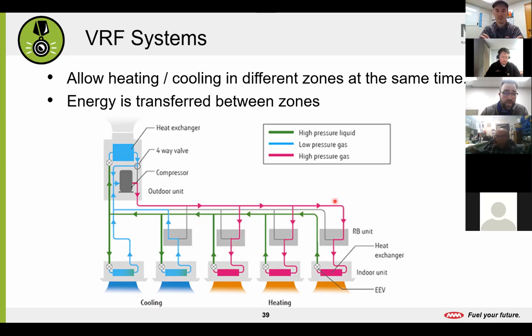Here we have hot gas coming in to our zone calling for heat, and it sends that gas through this rectangle right here. This is our coil. This is where our heat exchange happens. So our blower motor is going to push air across that hot coil. It's going to collect that heat, and it's going to push that into the space. What comes out of these systems is going to be a medium temperature liquid. Now, this medium temperature liquid is required for cooling operation.